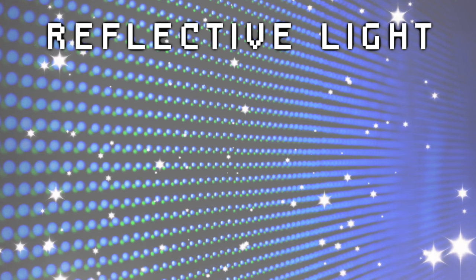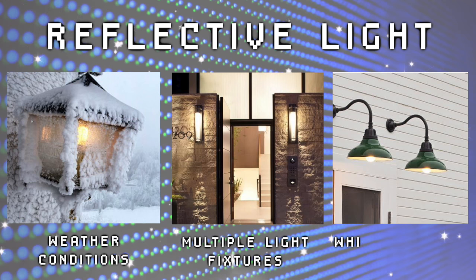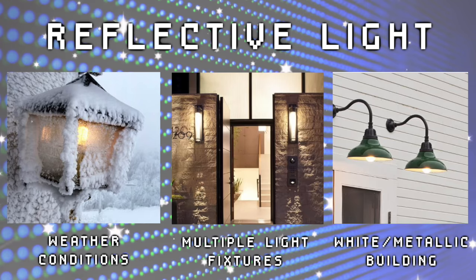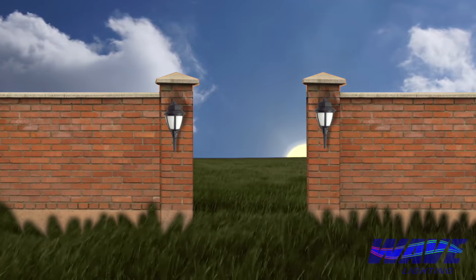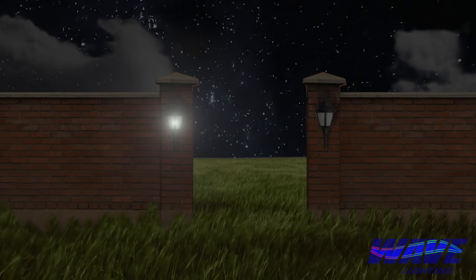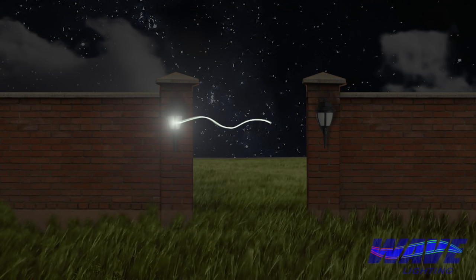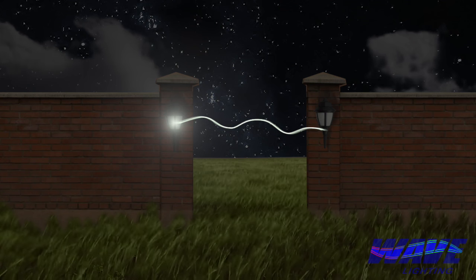One of the first application issues to consider is reflective light. Certain weather conditions, multiple light fixtures, or a white or metallic building may reflect light onto the photocell and trick it into thinking it is daytime when it is not. For instance, these two fixtures are within line of sight of each other. As the sun goes down, fixture A's photocell senses the absence of light and turns on, but fixture B is a second behind, and even though there is no sunlight, it is now sensing the light emitting from fixture A and will not turn on.